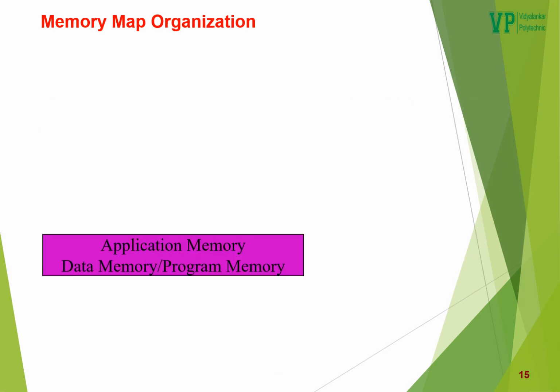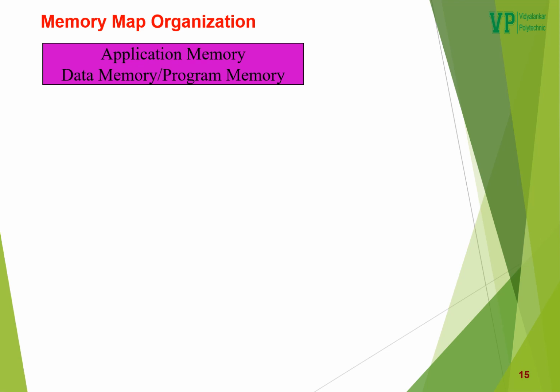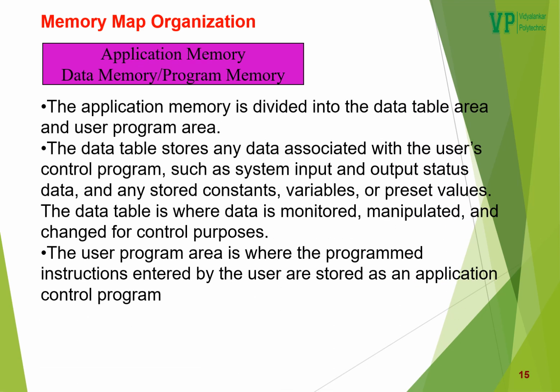The other part of PLC memory is application memory. The application memory is divided into the data table area and user program area. The data table stores any data associated with user's control program, such as system input and output status data, and any stored constants, variables, or preset values. The data table is where data is monitored, manipulated, and changed for control purposes. The user program area is where the programmed instructions entered by the user are stored as an application control program.